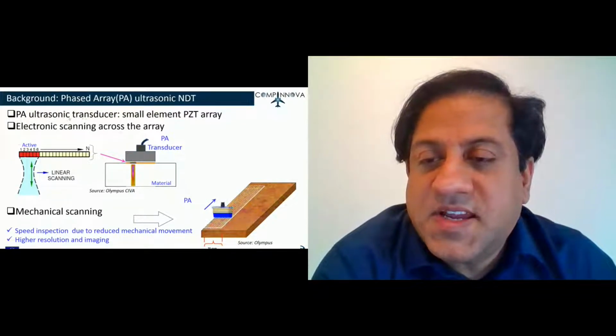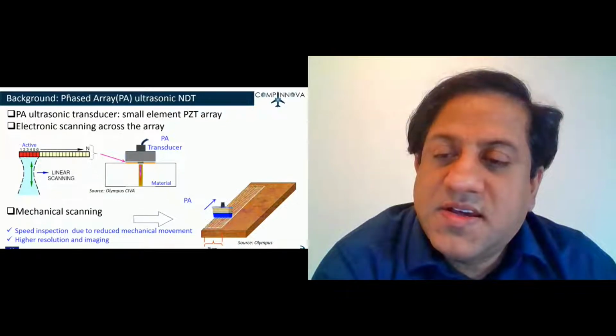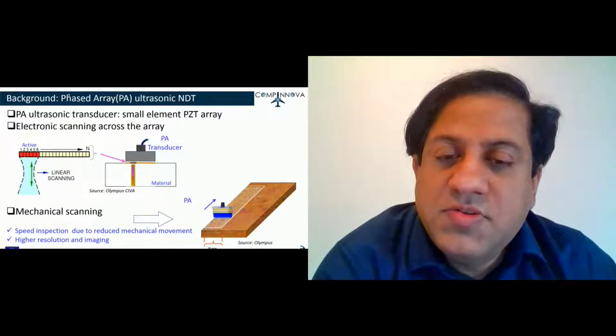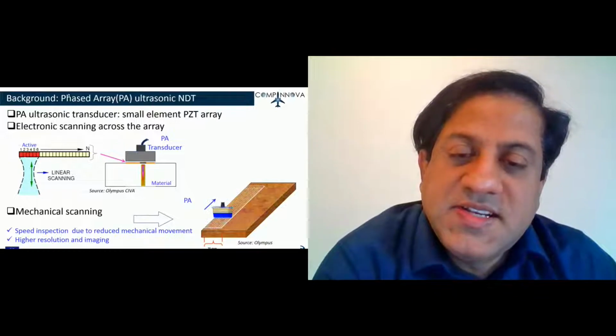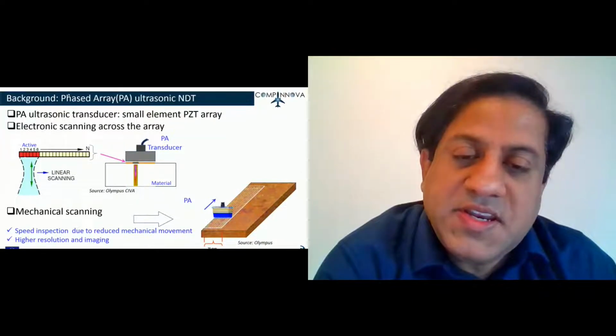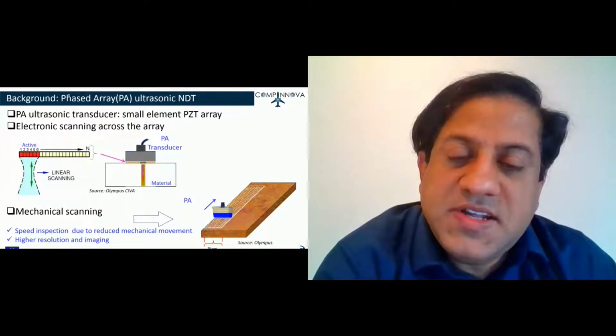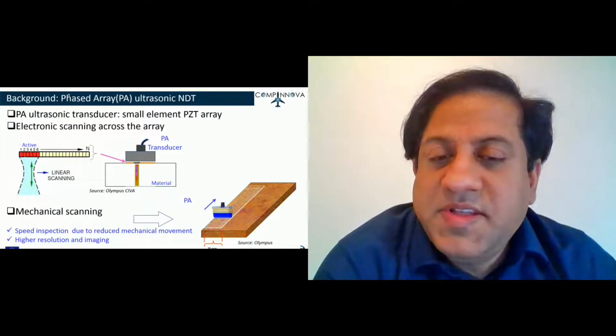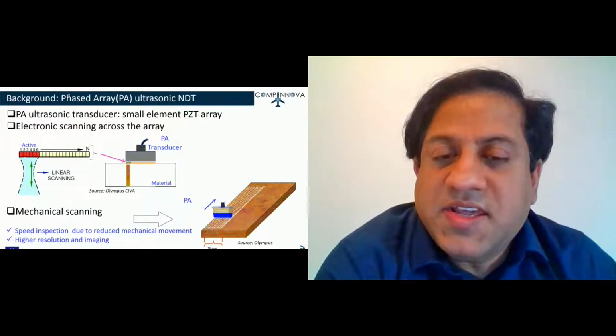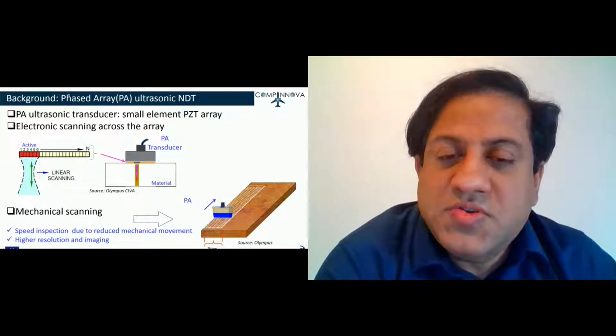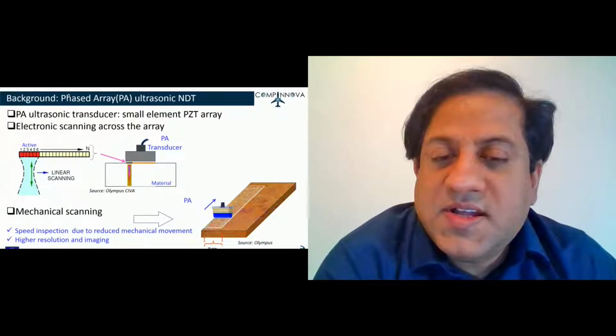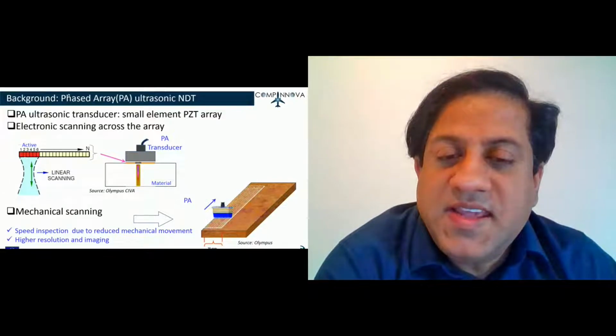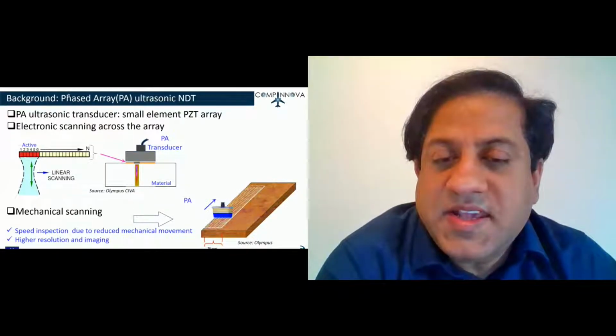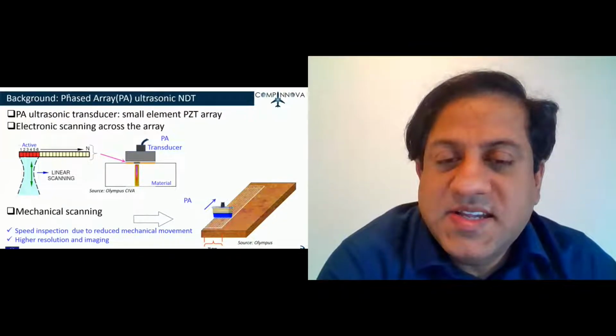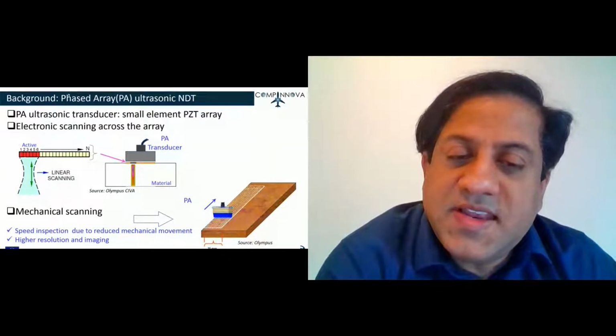On the left side, you can see a schematic of how the transducer sends the ultrasonic beam into the material, and it is recaptured, and that beam is traversed electronically from one end of the transducer to the other. So there is no need of scanning in one direction, whereas there is a mechanical scanning required in the other direction. Hence, this kind of scanning is much faster.